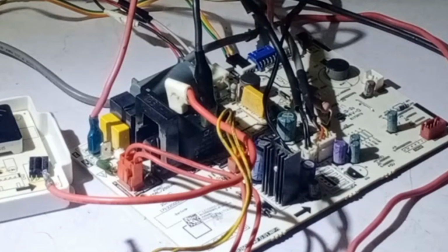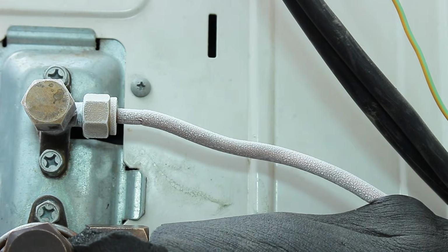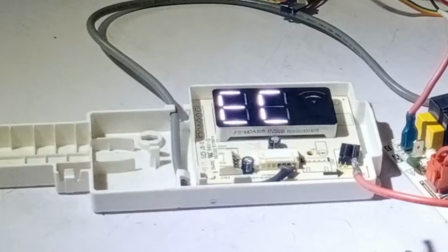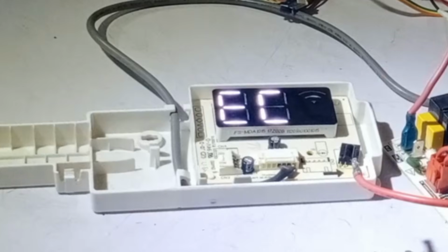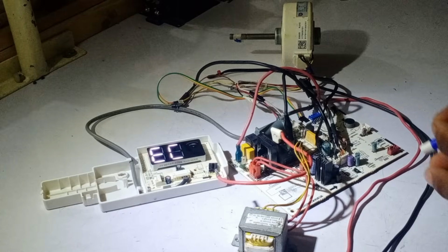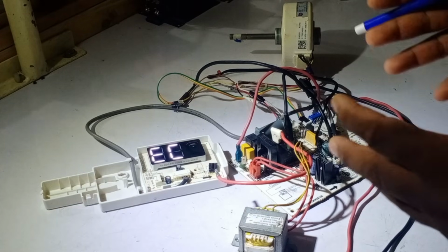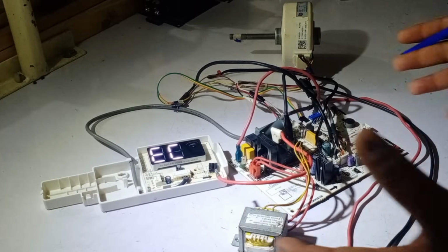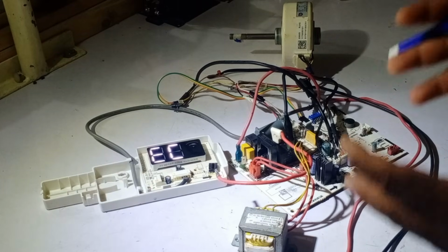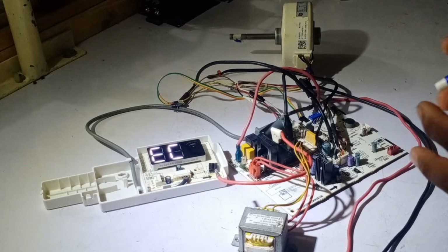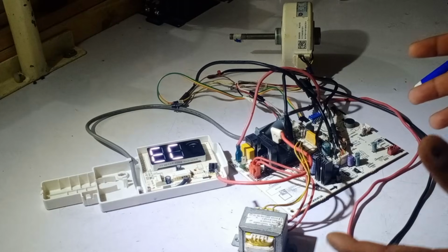Now if the refrigerant is decreased in the unit and ice is built on the discharge pipe, still, your non-inverter unit will show the EC error code. If the refrigerant from the unit is completely empty, still the unit will give you an EC error. There are many faults in the non-inverter mini split air conditioner when the EC error is shown. While in the DC inverter mini split air conditioner, if the compressor or the wire is bad, then those inverter air conditioners have different error codes for those problems. That unit gives different error codes for different problems.